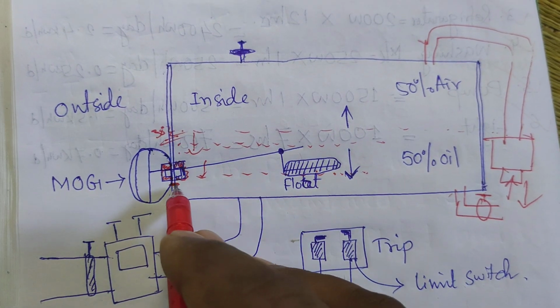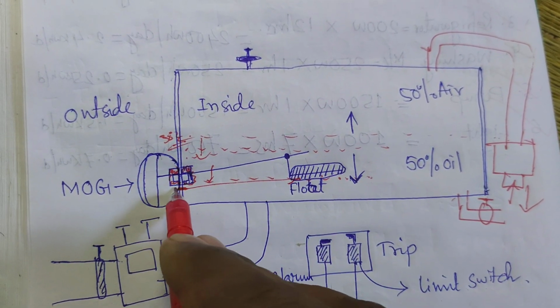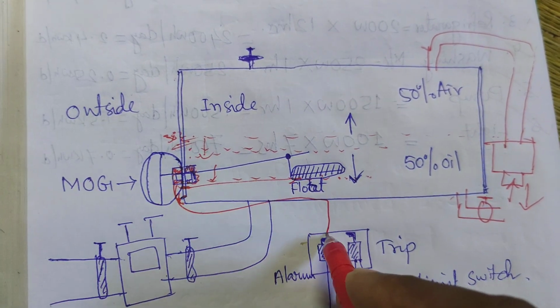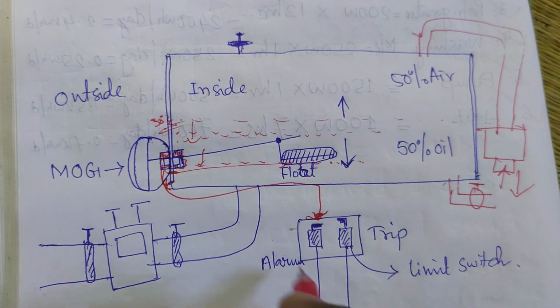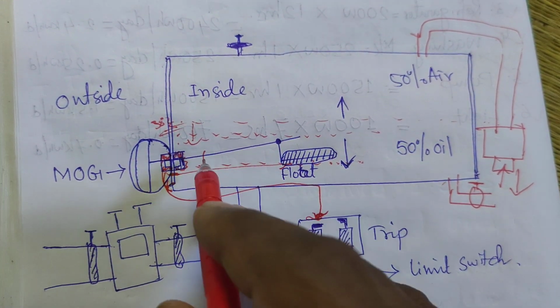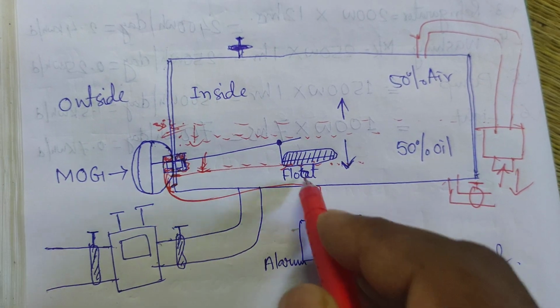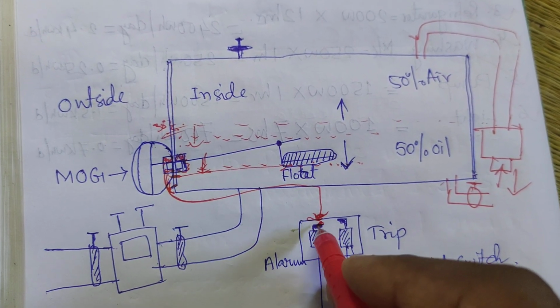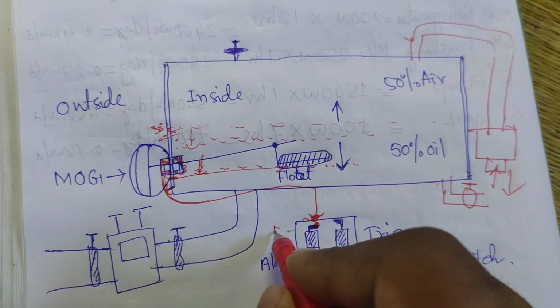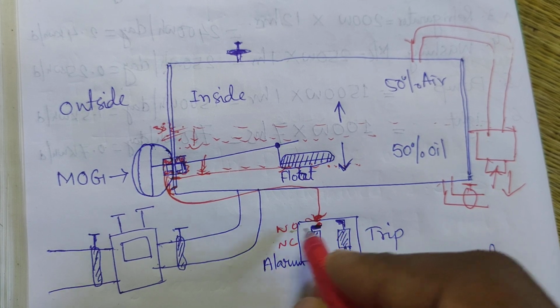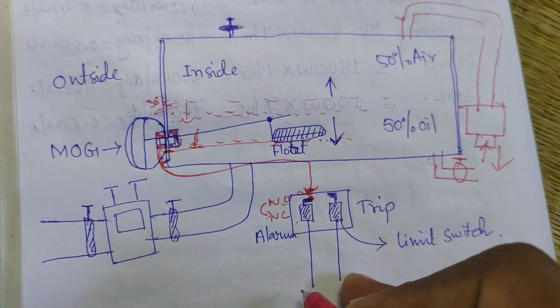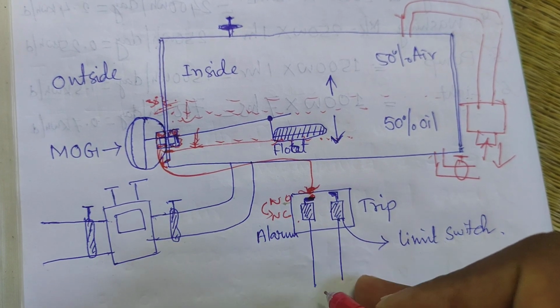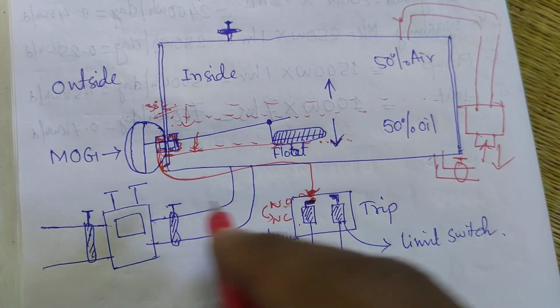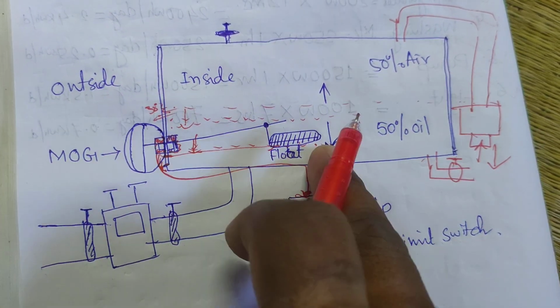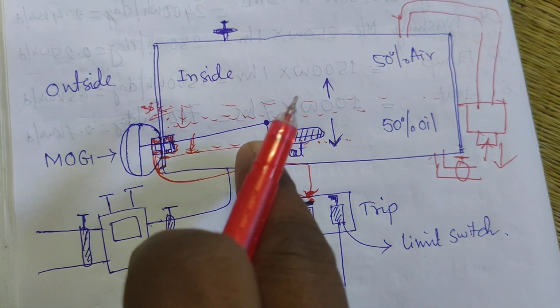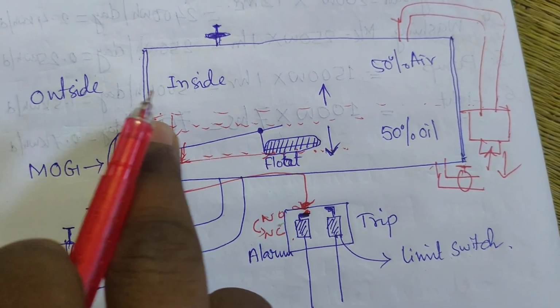If this float reaches the alarm position, there is a flange here. This flange is connected with the auxiliary contacts. If the oil level gets down to this level, this flange will operate this limit switch, and this limit switch has an NO-NC contact. This NO contact will become NC, and the DC will pass through the annunciator and the hooter will sound. That means the oil level of the transformer or the conservator is low. You have to fill the oil accordingly to 30 degrees Celsius for the betterment of the transformer.